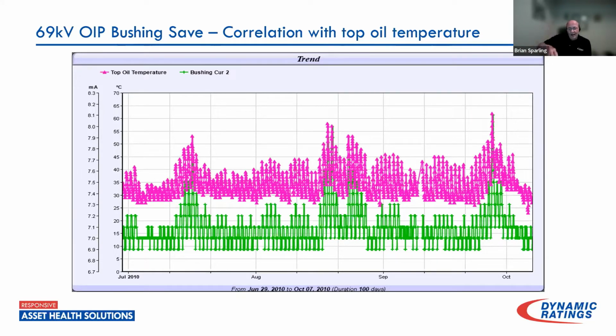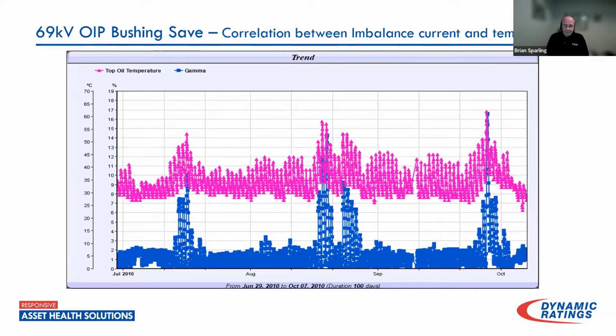So it's the indication of an incipient failure condition beginning to happen inside the bushing. And as always, the first clue that something is going wrong inside, the monitor will alarm and present you with the data. Here's what's happening inside your bushing. So in this case, this bushing was, we call, saved from the point of view of early warning of a bushing in failure condition.